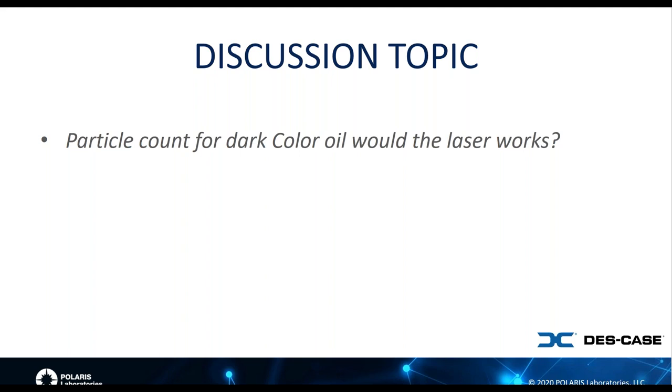We've used particle counting even on diesel engine oils, and I absolutely agree with the previous comments. It's not standard to do that on diesel engine oils, and you don't need to do it on every one. But if you're adding, for example, supplemental bypass filtration and you want to validate that the filter is doing the job, as you mentioned, Bob, labs can do a dilution. It's typically a 10-to-1 dilution, and there are ways that we can get around the color of the fluid. Typically with our darker fluids like gear oils or engine oils, we're not as interested in the particle count anyway. But if you are trying to monitor it, the dilution methods that Bob and Julio mentioned are a good way to do that. And having been through the lab there, Bob, I know you guys can do that. I've had some good data from your lab, specifically on engine oil particle counts, in support of a filtration project we were working on.